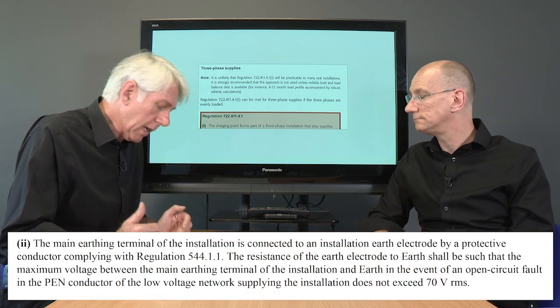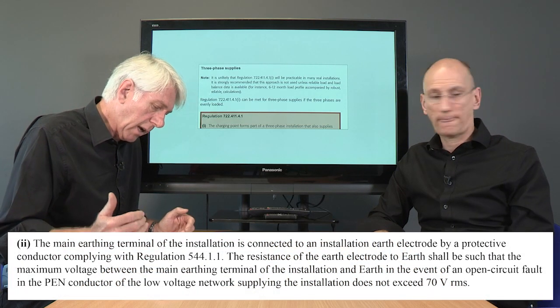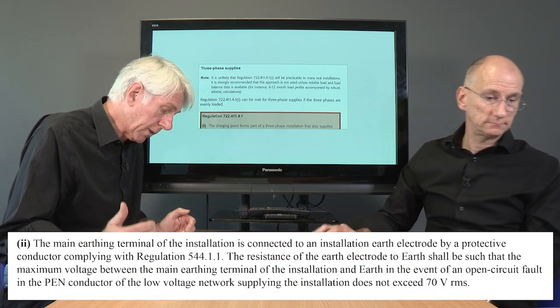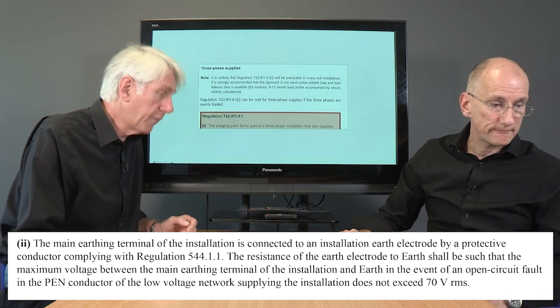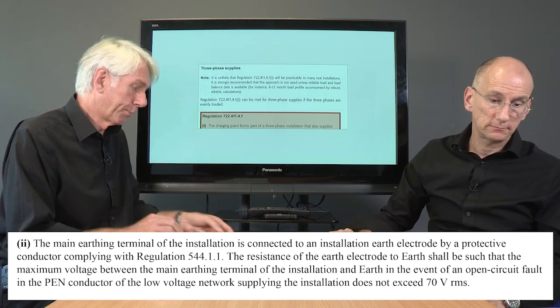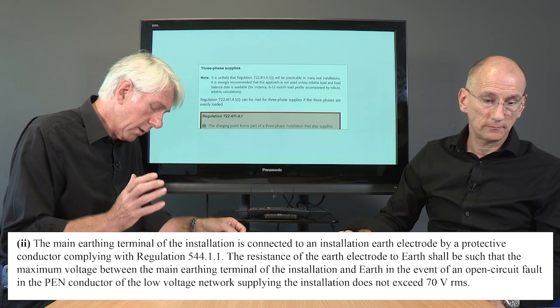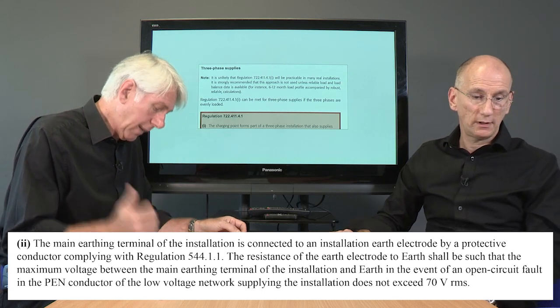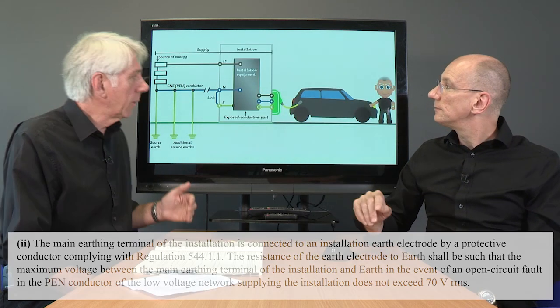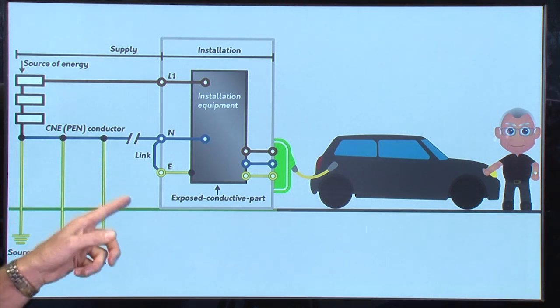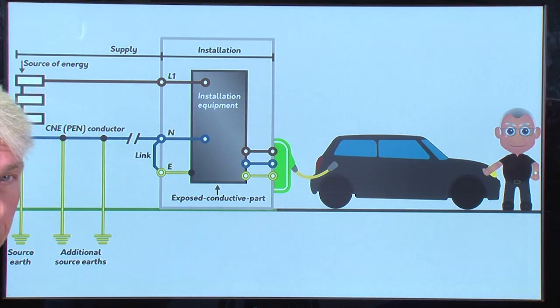So the next one was the main earthing terminal of the installation, connected to an installation earth electrode by a protective conductor complying with Regulation 544.1.1. So we took that and had a look at that. And this is all to do with the business of potentially losing the PEN conductor, a break in the PEN conductor, which would leave the installation vulnerable.